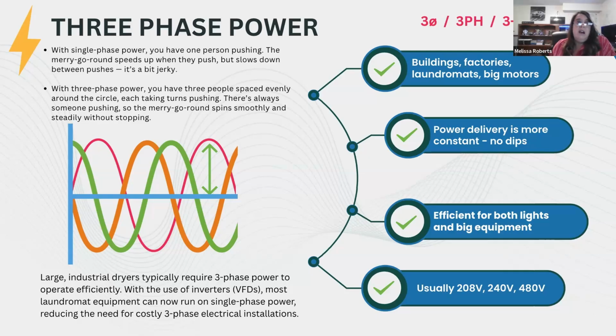That's three-phase power. Large industrial dryers typically require three-phase power to operate efficiently. However, with the use of inverters or VFDs, which we'll talk about a bit more, most laundromat equipment can now run on single-phase power, reducing the need for costly three-phase electrical installations. So if the building you're looking at already has three-phase power, perfect. If it doesn't, it's very expensive to get that power to the building, and with most new equipment nowadays, it's not necessary — you can run single-phase power and still have nice, efficient equipment.